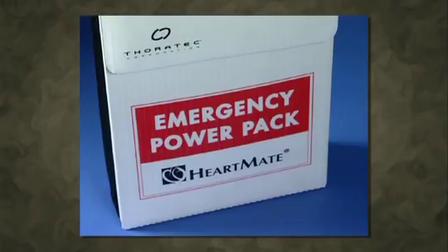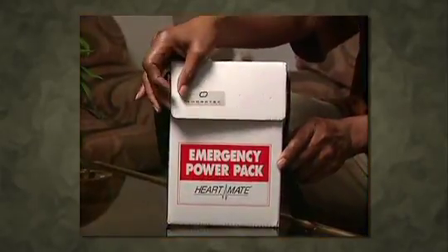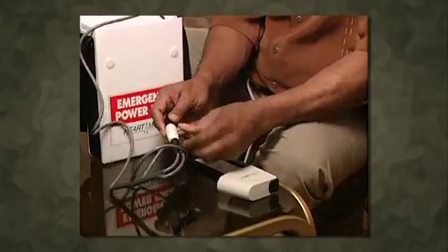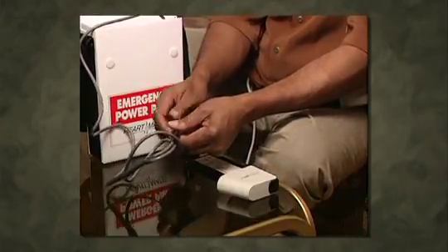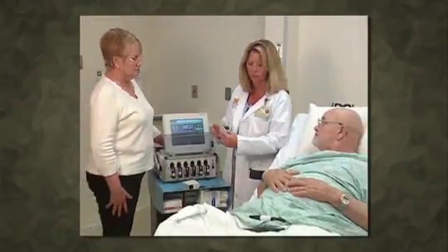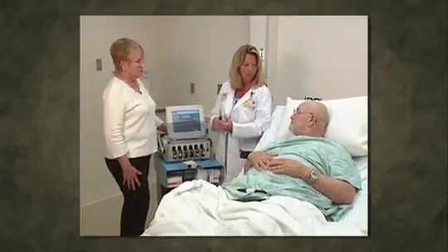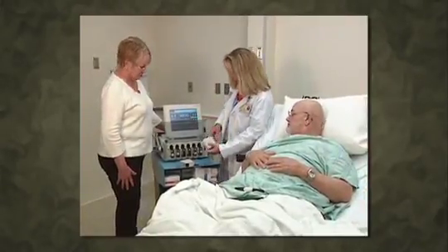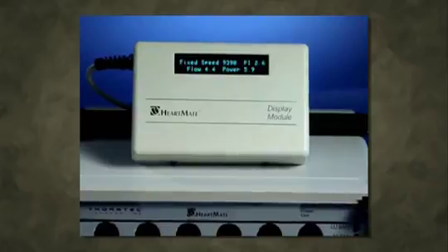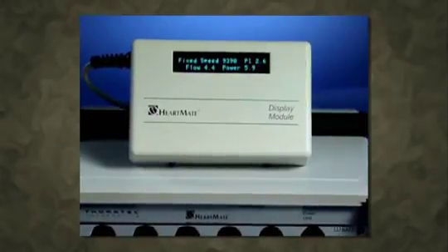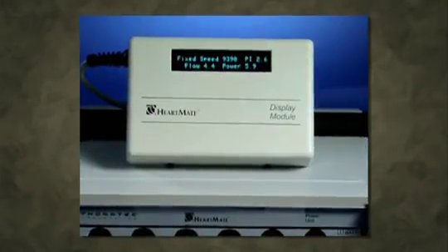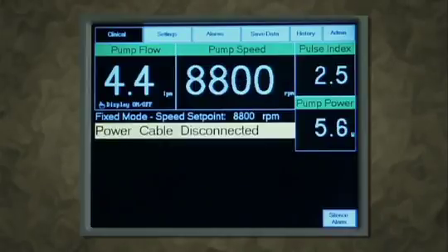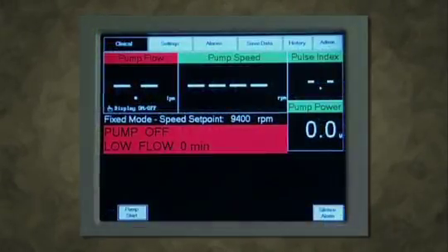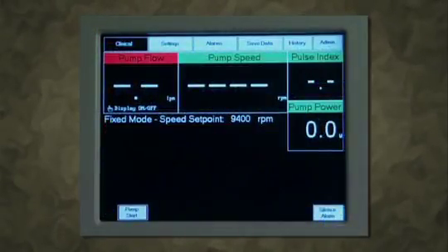Patients will also have an emergency power pack. This large battery is a one-time use energy source that can provide up to 12 hours of power in situations like a power outage. When the patient is connected to the power module, information from the system controller can be seen on a display module. This display shows how the pump is working by displaying information such as pump speed, flow rate, power, and other information that may be useful for the patient, as well as the LVAD coordinator at the patient's hospital.